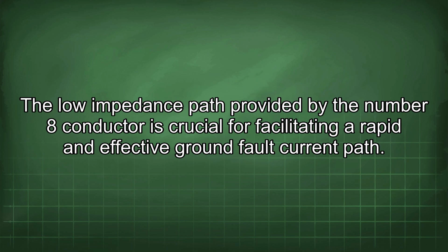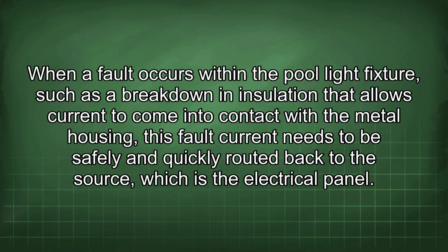The low impedance path provided by the number 8 conductor is crucial for facilitating a rapid and effective ground fault current path. When a fault occurs within the pool light fixture, such as a breakdown in insulation that allows current to come into contact with the metal housing, this fault current needs to be safely and quickly routed back to the source, which is the electrical panel.